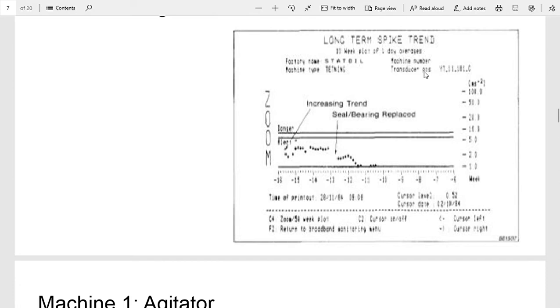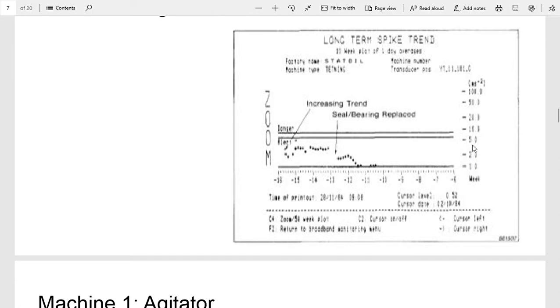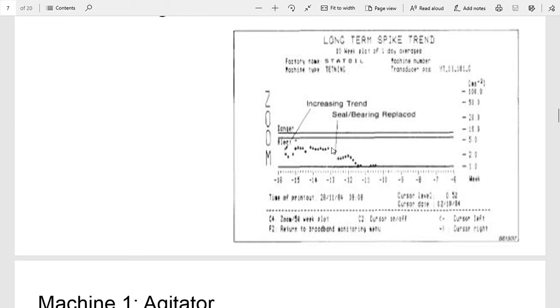So the first thing they found with the agitator was, if you look at this graph, this is time versus hertz. As you can see, there's an increasing trend here. So at a plant production stop, they replaced the bearing in the seal. When they inspected the bearing, they found that there was a spall in the outer race.